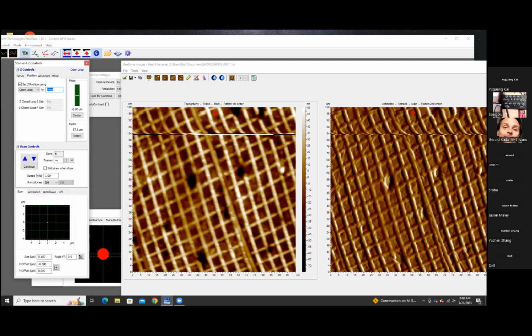And now we're going to do the same thing with the X and Y offsets. So with the X offset, put an obnoxiously high number for positive. Y offset, put an obnoxiously high number for positive as well. Okay, X offset, I'm going to do 999. And then Y offset, go to 999. It's only 5 to 4 micron. And that moves the position of those power supplies to their extreme on one side. So as you measure your negative X, you should get positive 200 volts.